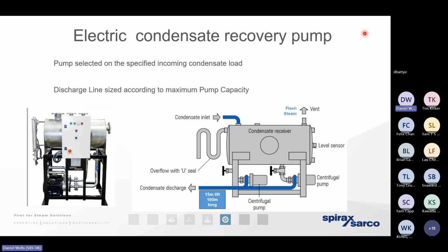So it's vitally important that that receiver's sized not just on the mass of condensate that's going to be produced. And remember, that's determined by the dryness of the steam, but we also need to allow for that condensate to fall in temperature and fall in pressure, so that it can cool down where it's not going to create a problem for those pumps. The good news is once that condensate's cooled down, we can bring it back to the boiler house in a much, much smaller single phase pumped infrastructure than one of those mechanical pumps.